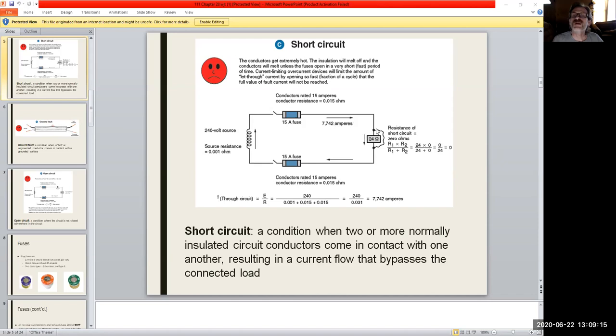So our current stays really low, but we get no work output. Basically, whatever we have on this end, designed to be working under this amount of current, is not happening. So if this is, say, a light branch, you go to turn it on and nothing is happening at all. But your circuit breaker doesn't trip, so you're not pulling too much current. This is probably one of the more complex scenarios you would run into out there trying to figure out what exactly happened. And it does happen, and a lot of times what you'll end up doing, unfortunately, is repulling the wire, because now your wiring's been compromised. This happens in a lot of instances: storefronts, homes, industrial settings. For whatever reason, something occurred, and we ended up with a short circuit.